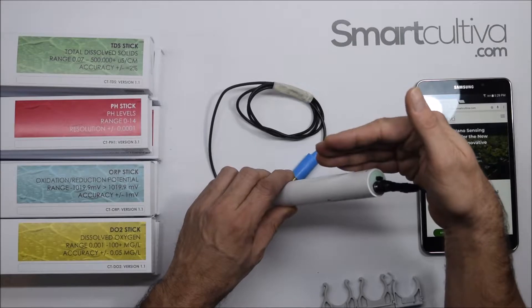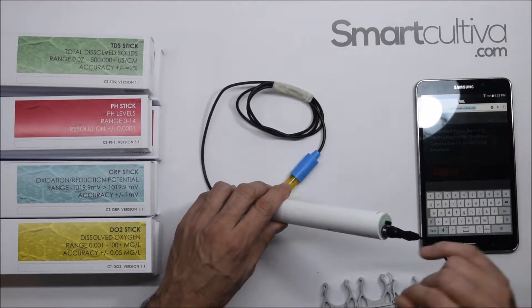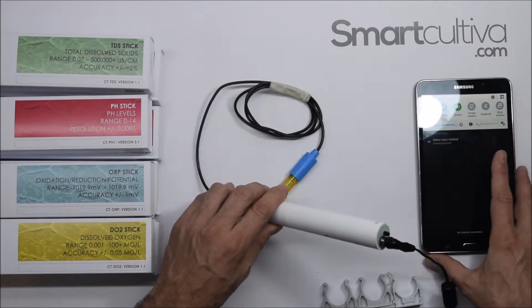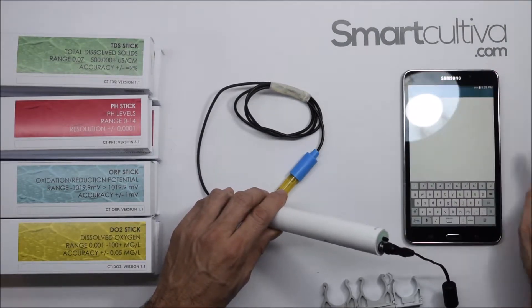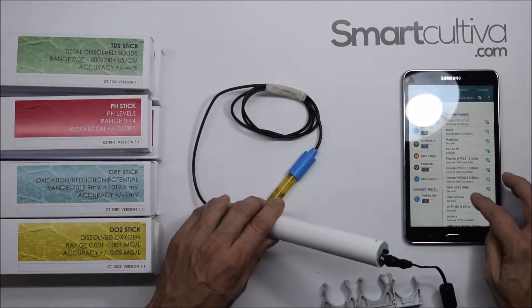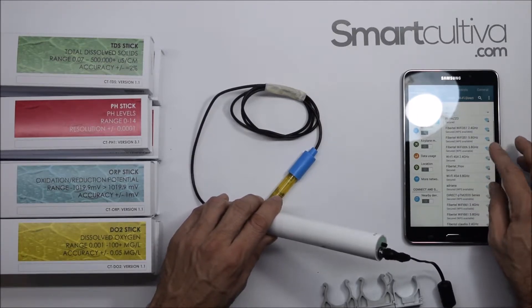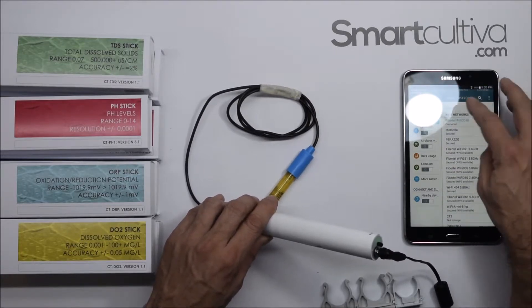When the sensor is initiated, you will see a red-blue light. The green-blue light indicates it is ready to connect to the server. It will enter the Wi-Fi network, and we will try to see if the device appears here. We refresh the server and yes, we have the connection.